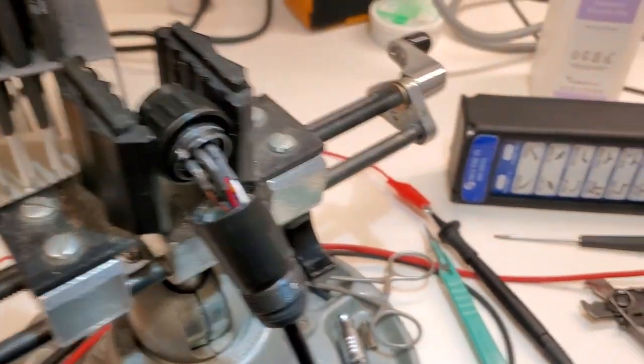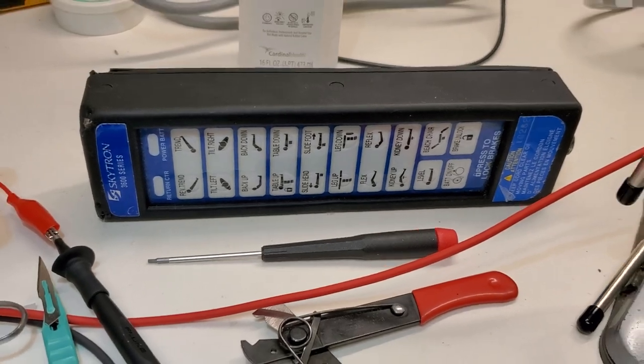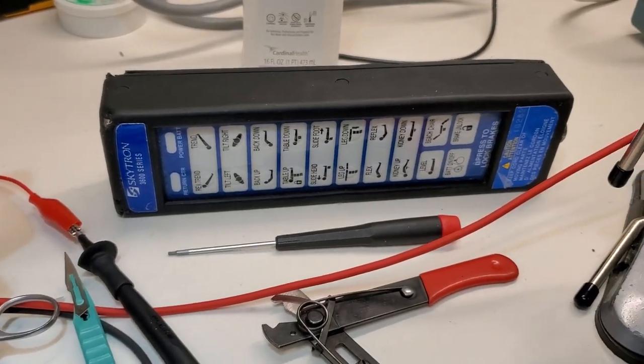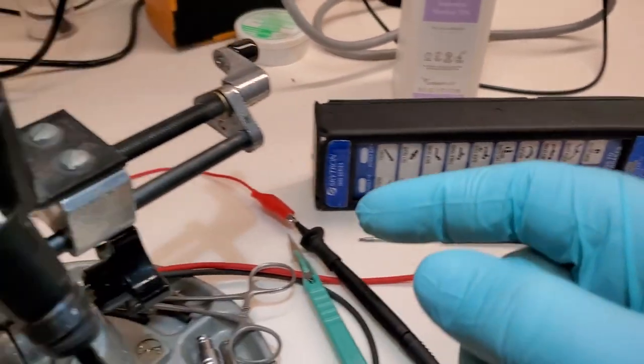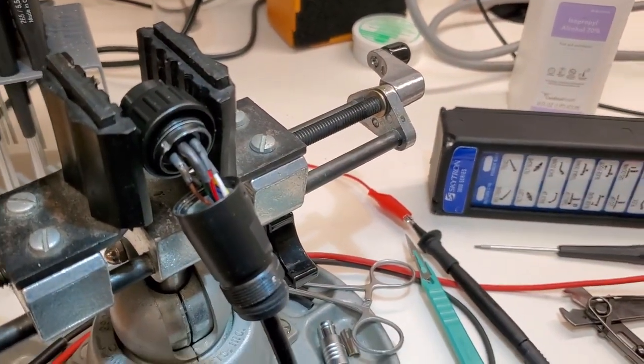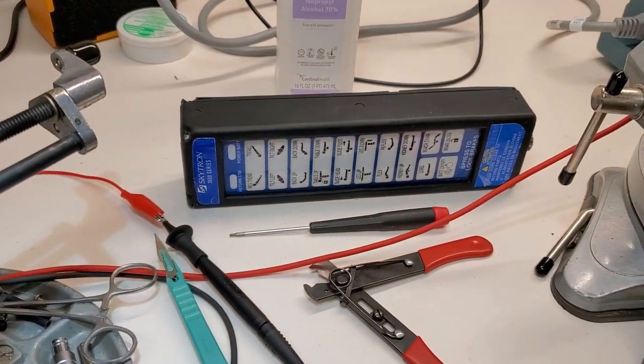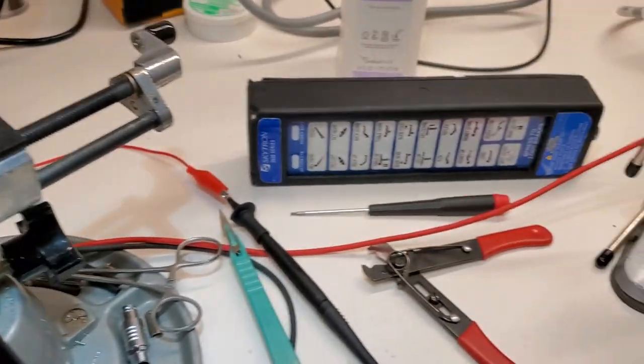Okay guys that's all I've got for you right now. This is a Skytron 3600 series. And this is a problem that a lot of the Skytron series seem to have. It is usually down at this end. But this time it's down here. Broken wires. That's it. Why buy a $2200 or $2300 remote when we can just fix them? Thanks for watching guys.